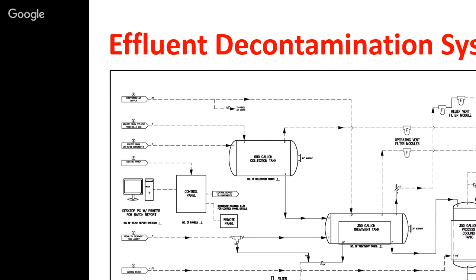The way this works is you have a collection tank that gathers all the water from the lab. And then you have a treatment tank. So this is always acting as a buffer so that the treatment tank can do its kill process and you never have to turn the water off upstairs. You just let this tank keep collecting. After the treatment's done, this tank then discharges to a cooling tank where they introduce the heat exchange or domestic water to cool it down, and then that's discarded. All of the fluid transfer between these tanks is done by compressed air. There's no pumps or anything. It's just high pressure air pushing the fluid between the tanks.